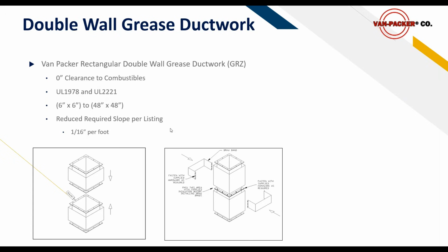One other addition to these is a reduced slope requirement. With factory built grease duct, you can actually reduce the slope requirement for these runs. And I apologize, there's actually a typo on this slide right here. It should actually be 1/8 of an inch per foot. So with a field welded grease duct system on horizontal runs, you need to have a 1/4 of an inch per foot slope back to a hood or back to a grease trap, just to prevent the grease. You want the grease going back to somewhere where it can be captured. With factory built grease duct, you can reduce that to 1/8 of an inch per foot. So I apologize for that typo, but that is a benefit as well for factory built grease duct, and that applies to Van Packer or Jeremiah's.